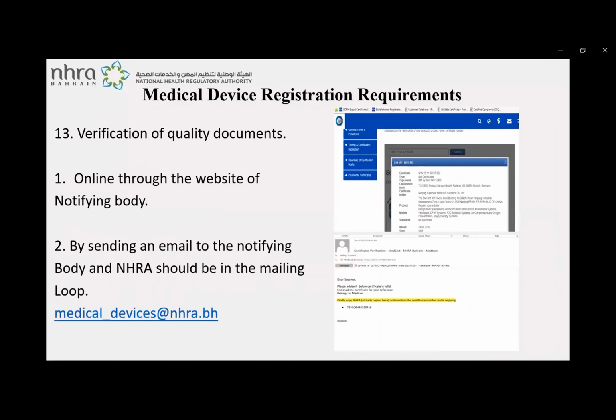All right. Now, before submitting any of the last 3 documents, the QAC, QMS, and the EC design examination, the applicant needs to make sure that they are still valid, because notifying bodies have periodic or regular audits to the manufacturer. So it is often that certificates get cancelled before their actual expiry date. To do verification, there are 2 ways. Number 1 is online through the website of the notifying body. You can find the verification link of most notifying bodies on the NHRA website. And verifying by website is done by entering the certificate number or the name of the manufacturer into the database search, depending on the notifying body.